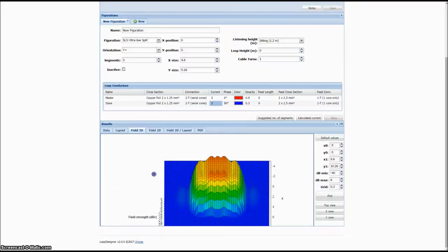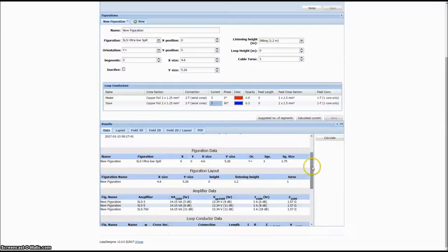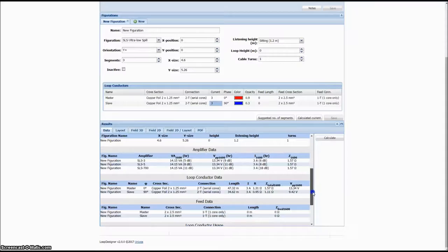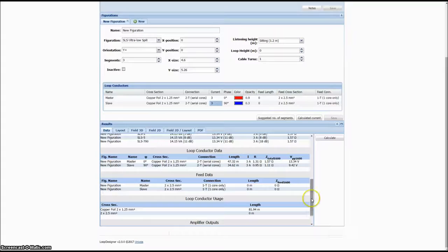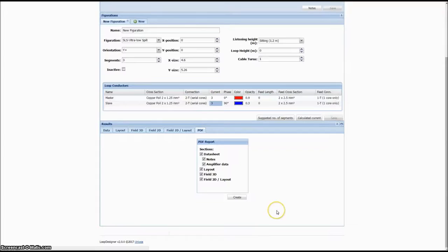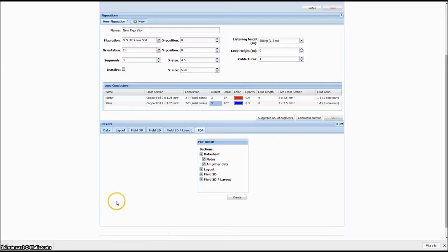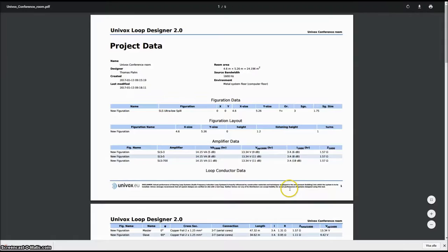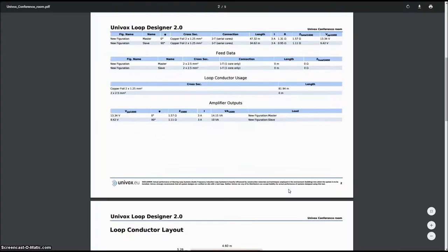Once we are contented with the projected performance of the loop, we return to the results part, the data tab, and again click on calculate. The designer software will now list all loop amplifiers that can be considered for the project. It will also tell us the size of the loop, the width of each segment, and the length of wire needed for the installation. We can then download a PDF report to share with project partners and customers. The report includes cable layout, performance graphs, and all the result details.